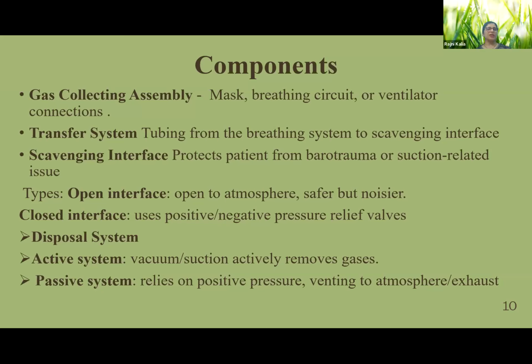The gas collecting assembly will include the mask, breathing circuit, or ventilator connection, and the transfer system, including the breathing system to the scavenging interface. The scavenging interface can be open or closed, and it protects the patient from barotrauma or suction related issues. The open interface basically releases the gases to the atmosphere directly, and the closed one uses positive or negative pressure relief valves.